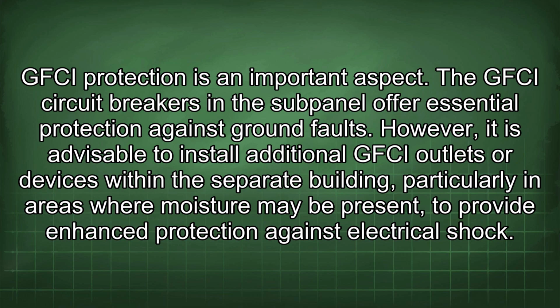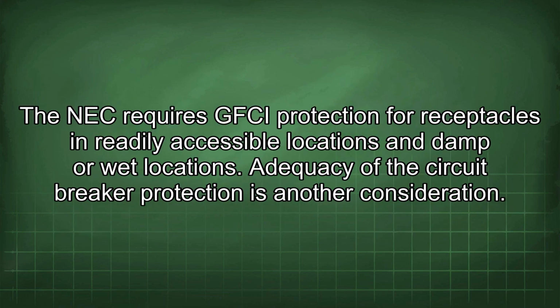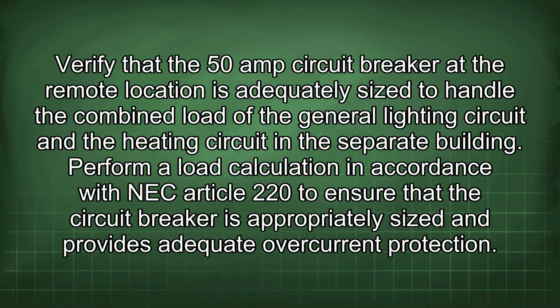GFCI protection is an important aspect. The GFCI circuit breakers in the subpanel offer essential protection against ground faults. However, it is advisable to install additional GFCI outlets or devices within the separate building, particularly in areas where moisture may be present, to provide enhanced protection against electrical shock. The NEC requires GFCI protection for receptacles in readily accessible locations and damp or wet locations. Adequacy of the circuit breaker protection is another consideration. Verify that the 50 amp circuit breaker at the remote location is adequately sized to handle the combined load of the general lighting circuit and the heating circuit in the separate building.